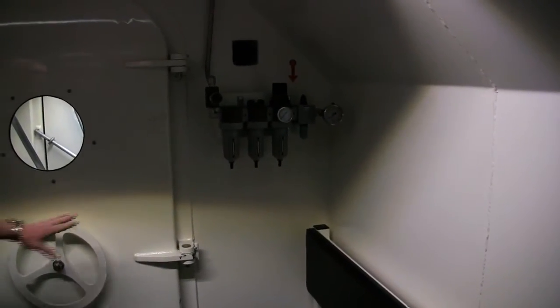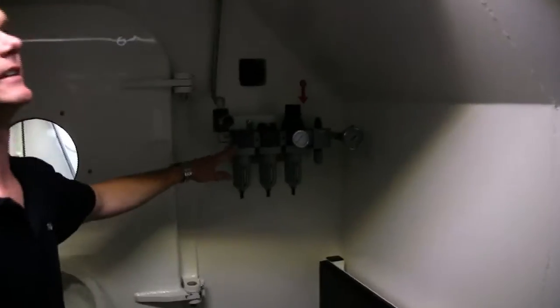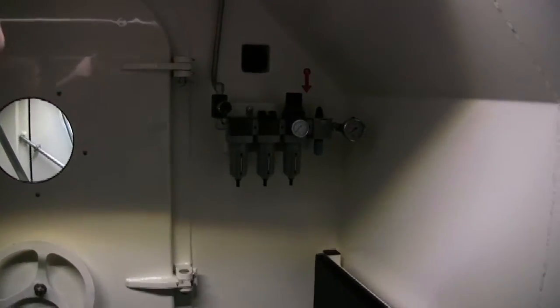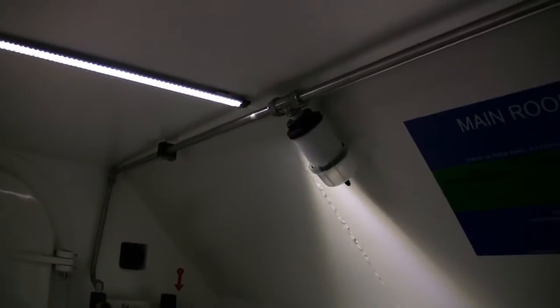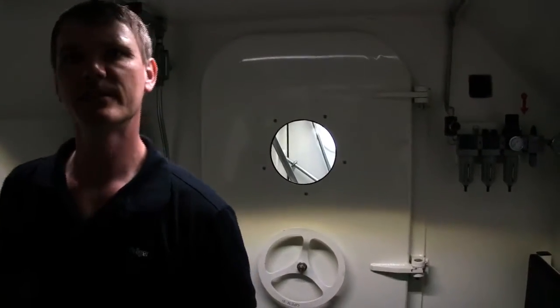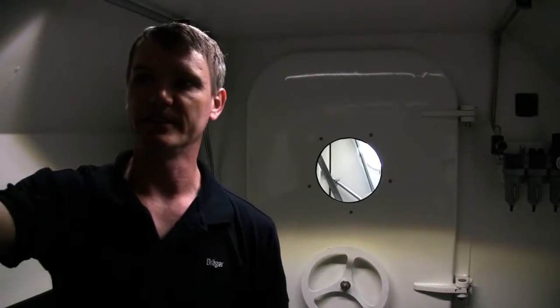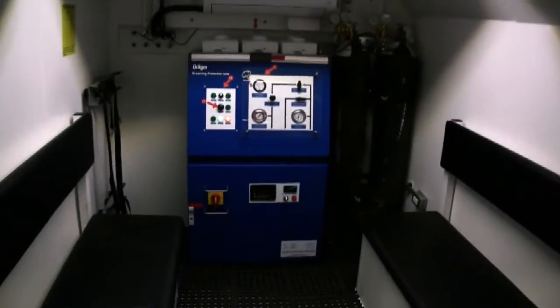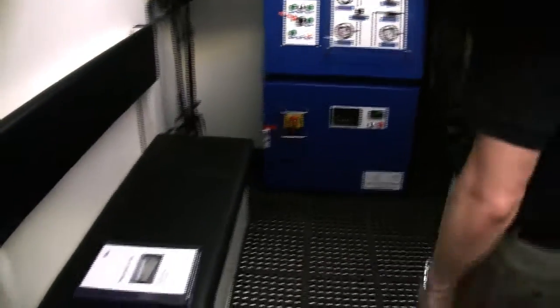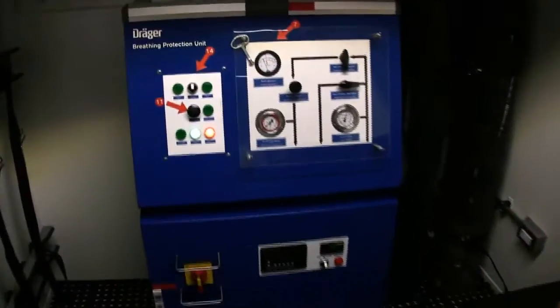Again this is a three stage filter system from the main air which comes through silencers. So it doesn't deafen people. We put 1200 litres a minute through here. That creates a positive pressure in here, approximately 400 Pascals. You can see the front door is closed. You and I in here generating heat. Each person puts off about 100 watts. So we're actually building pressure in here just by being in here breathing and our metabolic heat generation. So we're about 100 Pascals right now just as we idly stand here.